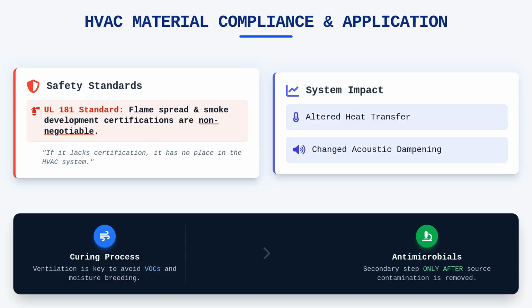Compliance with safety standards is non-negotiable when selecting materials, specifically regarding UL 181 standards for fire and smoke ratings. A product might look effective, but if it does not possess the appropriate flame spread and smoke development certifications, it has no place in an HVAC system. We also have to consider the long-term impact on the system's thermal and acoustic properties. Adding a thick layer of coating can slightly alter the heat transfer capabilities of the ductwork and might change the acoustic dampening profile of the internal lining.